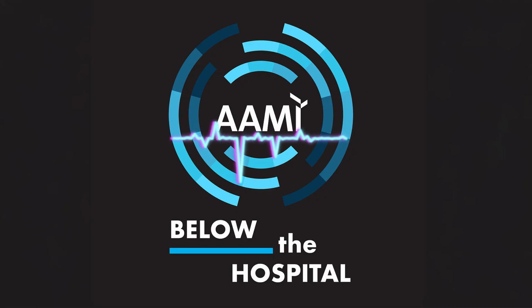Most wrap failures are linked to mechanical causes, as well as something you brought up earlier, which I think hones in on wet packs. Let drying do its job. If wet packs are reoccurring, treat it as a system issue: set weight, absorbent materials, tray design, wrap selection, load configuration, and cycle and drying parameters or settings. ST79 is what facilities often lean on for investigating these issues with steam sterilization programs, right?